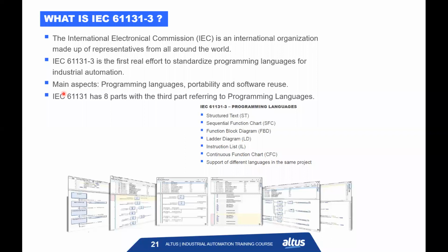The main aspects are programming language, portability, which is very important, and software reuse, to give the customer an easier way to reuse these. The IEC 61131 has 8 parts, and the third part refers exactly to the programming languages. So when you see a PLC that follows this standard, you will for sure find exactly these programming languages listed here: structured text, sequential function chart, function block diagram, ladder diagram, instruction list, and continuous function chart. Here is the graphic presentation of these: SFC, FBD, ladder, IL, and CFC here, and structured text here.